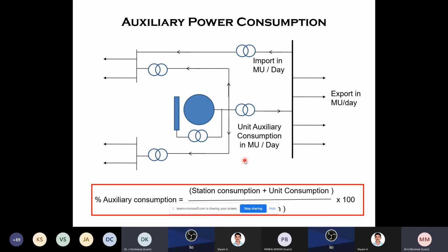So auxiliary power consumption will vary depending on the type of unit. Particularly for a lignite fired boiler, the auxiliary consumption is very high because we have to run the unit with lignite, whose calorific value is very low, about half that of coal. So we have to handle double the quantity of fuel, for which we need huge machinery for handling. And second, the ID fan and FD fan will be highly loaded because of the poor quality. That's why in a lignite fired plant, around 10% auxiliary power consumption is allowed by the Ministry of Power, or the CEA has given a relaxation of 10%.